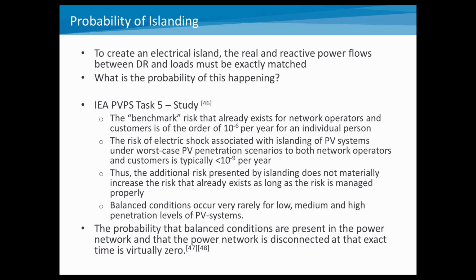So in general, the outputs of this, and you can read more about it in the reference that's on here, are that balance conditions are very rarely occurring, even at low, medium, or high penetration levels, and the probability that these balance conditions are present and that the network can sustain them and disconnect at that specific time is virtually zero. So there has been some work that has really identified what the probability of that could be addressed. Again, this is an area that you could do further research in.